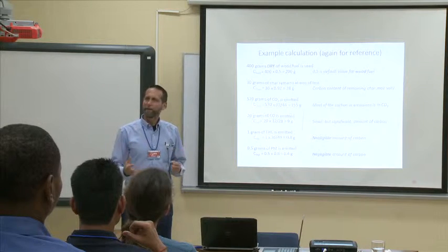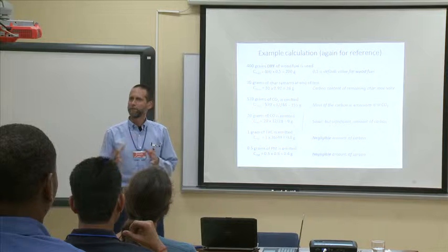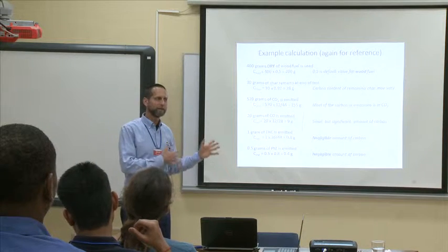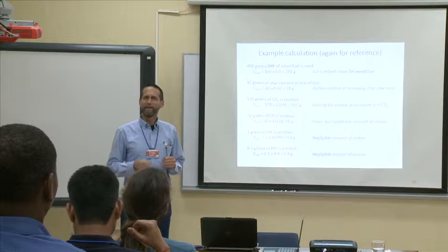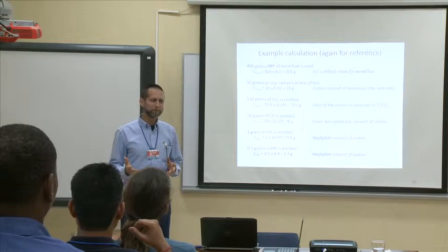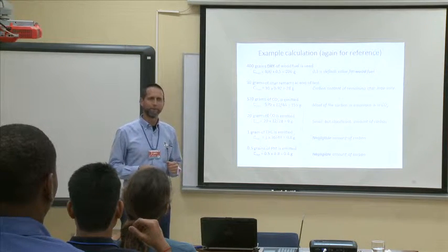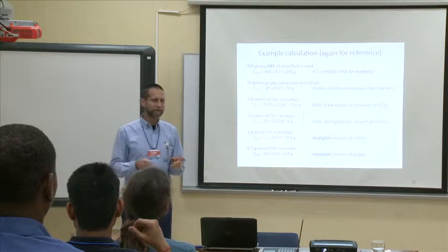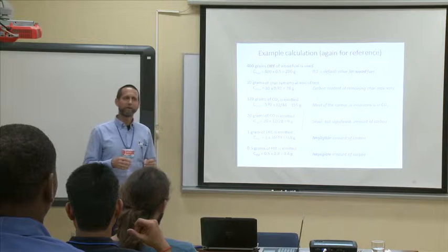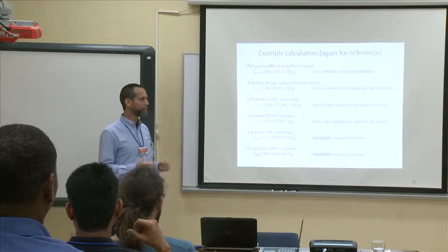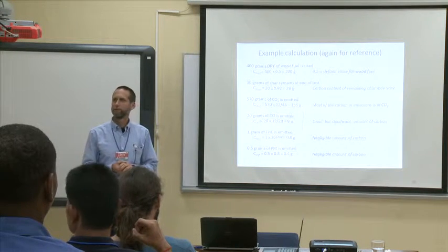And we kept hoping that we would find a problem with the airflow measurement that would explain the carbon balance being off. But we could not find it, and in the end, it turns out that it was not the airflow measurement. But that is an excellent point. Thank you, John, for making that point, because that will throw off your measurements and will affect your carbon balance.